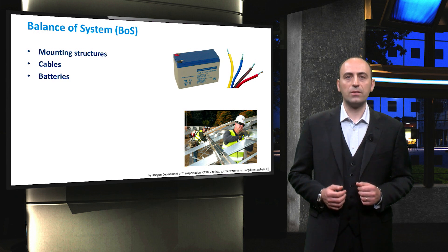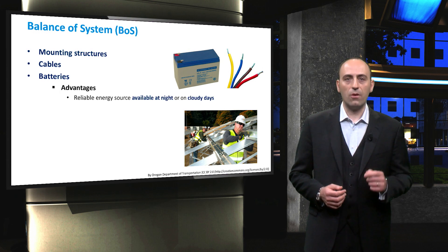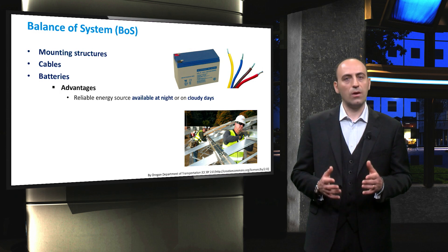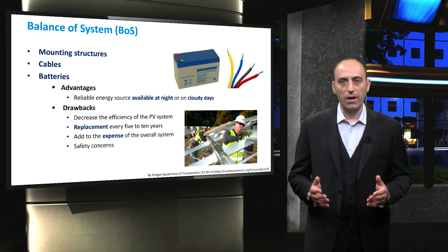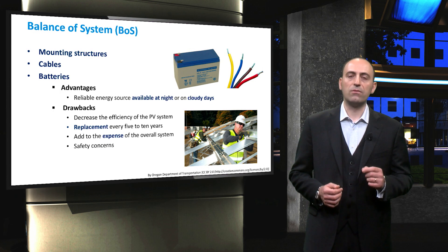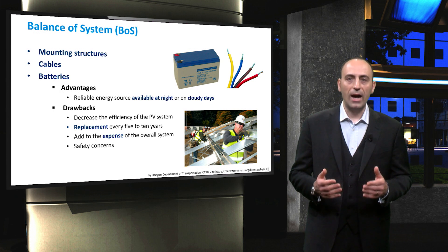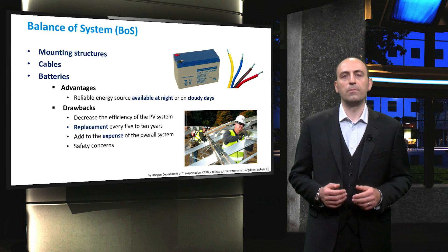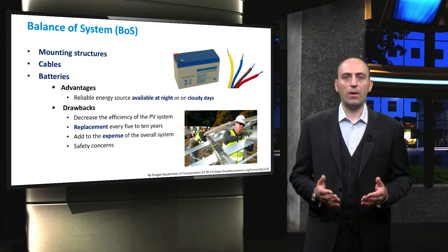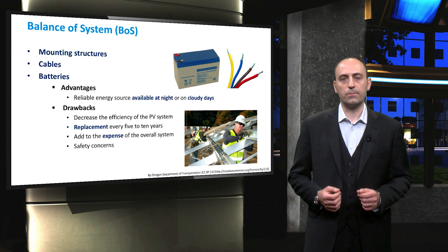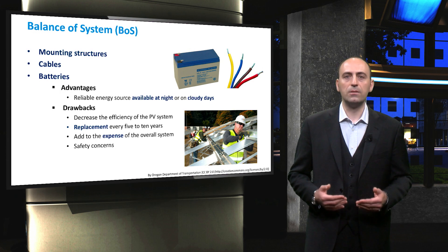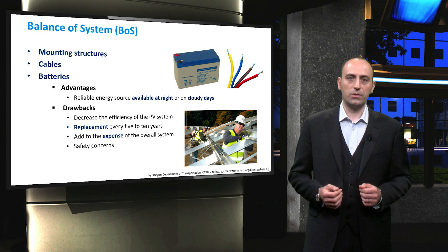Storage devices, like batteries, are also instrumental in standalone systems. The batteries provide a reliable source of power. As long as they are well maintained, they ensure that loads receive needed power during the night and in periods of bad weather. However, the balance of system components do have some drawbacks. When adding a component, the efficiency of the PV system decreases. This applies also for batteries, since they exhibit some thermal and chemical losses. In addition, they have to be replaced more often than other electrical components in the system.